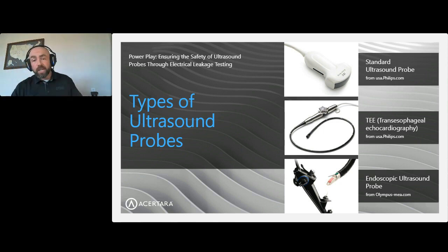Finally, jumping back to the slide, there are endoscopic ultrasound probes, and those are endoscopes that are used to gather visual information, and then the physician actually has the option to switch over or to simultaneously acquire ultrasound images from the tissue that they're looking at. And yes, Lisa, I do recommend that the leakage test be done before the high-level disinfection. Typically, the probes get rinsed and wiped down, so that you get the main bulk of patient material off of the probe. Once you've got your initial cleaning, I would do clean, then leakage test, then disinfect. Those steps.